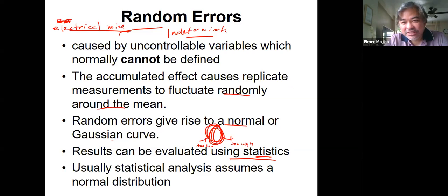When we get several readings, the cosmic rays disappear. So if it appears in just one of the 5 readings, if you average them, you could say that that's not really true, unlike the signal coming from the sample. Whatever happens, you will always have that signal when you get the reading multiple times.